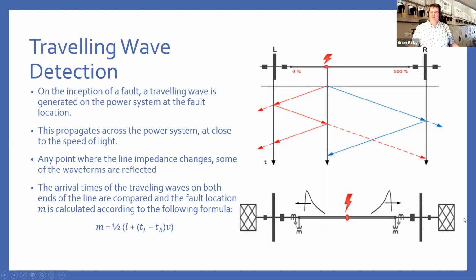And if you're measuring at both ends, and you can measure accurately the time it arrives at either end, you can use an equation like this one here to use the difference between the two time measurements to calculate where in percentage terms you are on the network.